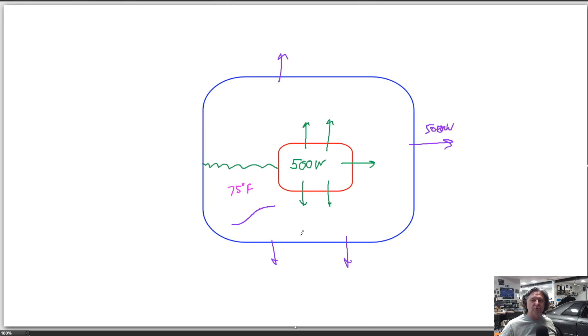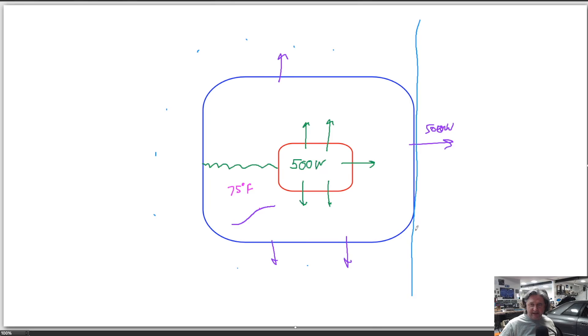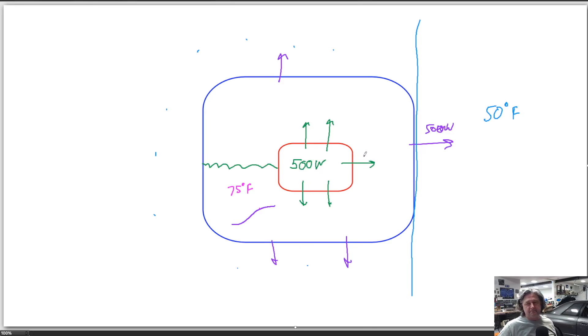The room itself can get rid of some heat via convection through the walls. If the room gets warmer, it heats the walls, which heats other parts of your house. If the room has an outside wall and the outside air temperature is say 50 degrees Fahrenheit, you can dissipate heat through that wall to the outside world. This depends on how much heat you're putting in, how well insulated the room is, and the outside or house air temperature. Generally, only a pretty small home lab can rely on this approach.